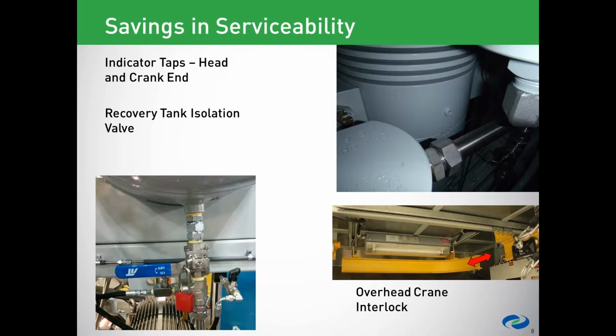We have included a recovery tank isolation valve that is installed between the recovery tank and the recovery tank relief valve. It comes with a lock and is locked in the open position during normal operation. Only during maintenance requirement on the relief valve would this valve be closed, and that allows the gas to be maintained inside of the recovery tank, which allows that gas to be saved rather than vented to atmosphere during maintenance. It also speeds up the service time because the service technician no longer needs to wait for the entire system to drain down in order to access that relief valve.